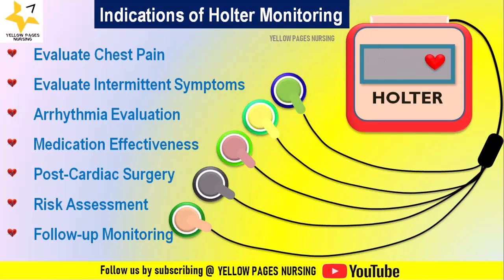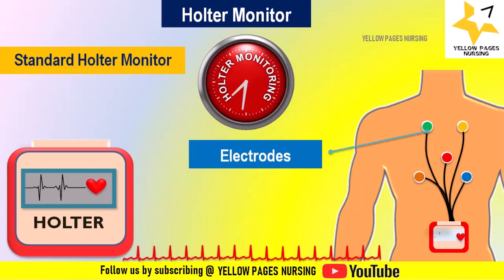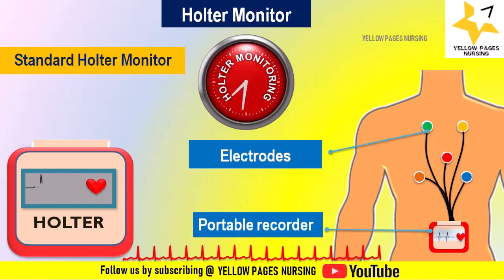Holter monitoring comes in various types, each serving specific purposes. The standard Holter monitor is a battery-operated portable device that measures and records the heart's ECG activity continuously. Electrodes are attached to the chest and the patient wears a small portable recorder. The metal electrodes conduct the heart's activity through wires into the Holter monitor where it is recorded over a 24 to 48 hour period. There may be a patient button on the front that the patient can press at specific instances.